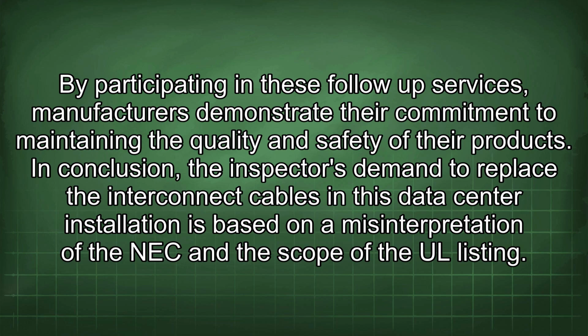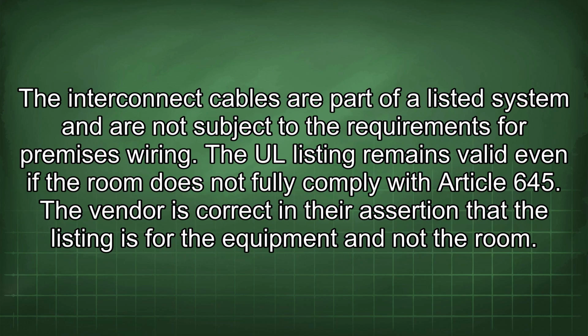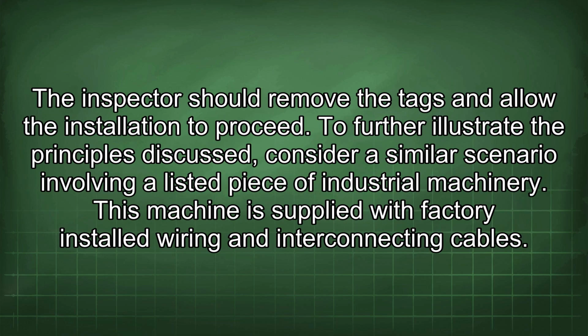In conclusion, the inspector's demand to replace the interconnect cables in this data center installation is based on a misinterpretation of the NEC and the scope of the UL listing. The interconnect cables are part of a listed system and are not subject to the requirements for premises wiring. The UL listing remains valid even if the room does not fully comply with Article 645. The vendor is correct in their assertion that the listing is for the equipment and not the room. The inspector should remove the tags and allow the installation to proceed.